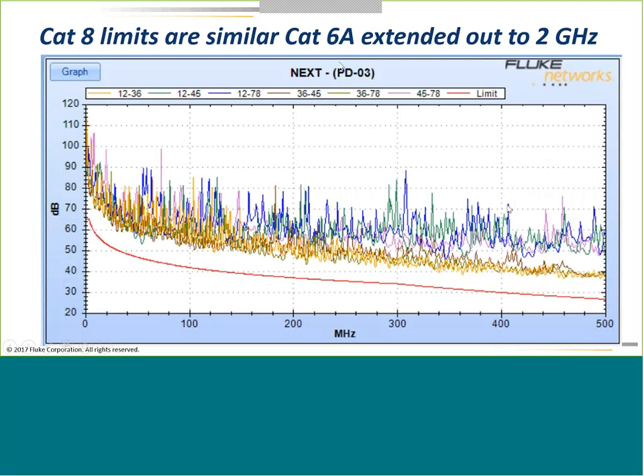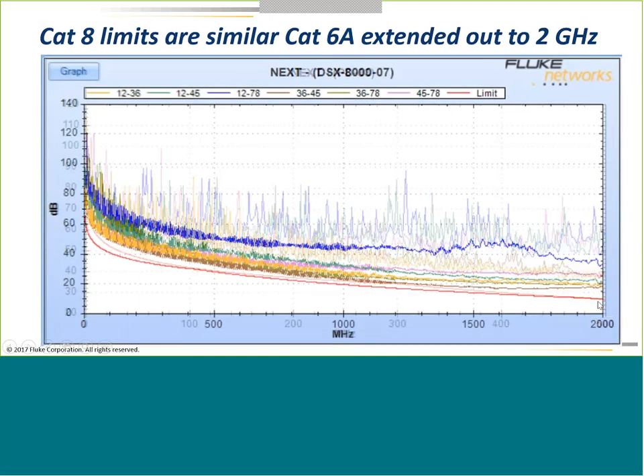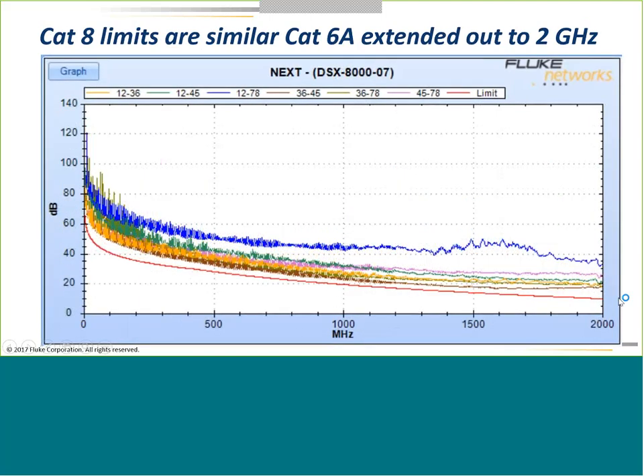Here's the NEXT graph — near-end crosstalk, the interference from one pair to another. On the vertical axis the strength of interference between pair combinations; on the horizontal axis frequency. Category 6A goes to 500 MHz — basically using the same limit line, we're just stretching it out to two gigahertz. Here is a passing NEXT measurement of a Category 8 link.